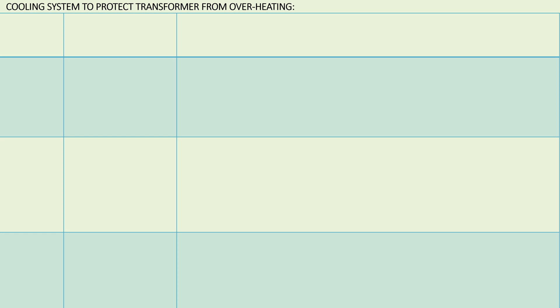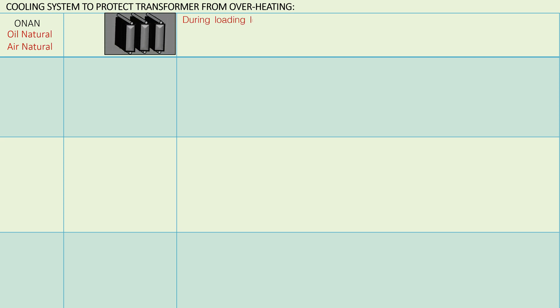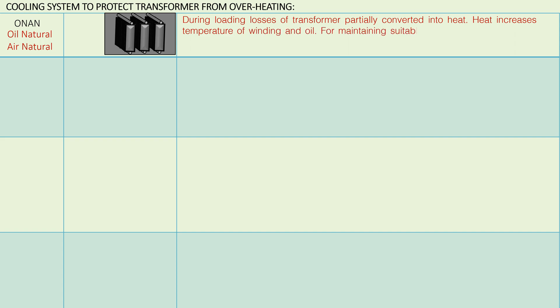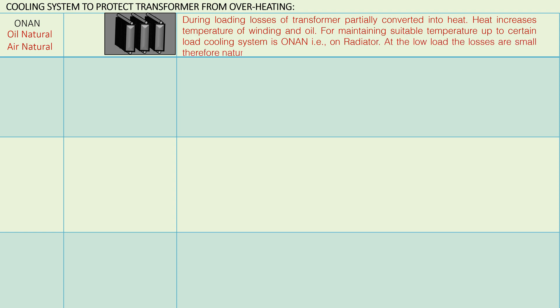Cooling system to protect transformer from overheating — ONAN (Oil Natural Air Natural): During loading, losses of transformers are partially converted into heat, which increases the temperature of the winding and oil. For maintaining a suitable temperature up to a certain load, the cooling system is on ONAN, that is on radiator. At low load, losses are small; therefore natural circulation of oil with ONAN is sufficient to cool the transformer.